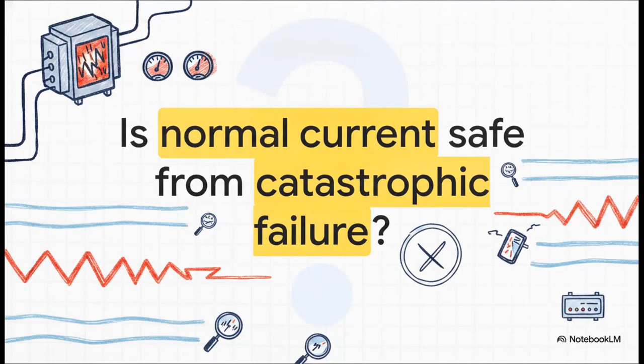So, let me ask you something. If a transformer's total load current looks completely normal, does that mean it's safe from a catastrophic failure? Well, here is what a lot of folks new to transformer protection get wrong. They look at the dials, they see the total current drawn from the network looks totally unremarkable, and they just assume everything is fine. But honestly, that assumption can lead straight to a destroyed transformer. Why? Because some of the absolute worst, most destructive faults don't immediately spike your overall load current. They kind of just hide in the details.